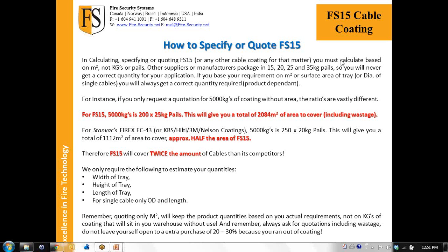But on top of that, one of the things is, as long as your machine is earthed, you're spraying live cable anyway. This is not a business interruption product. It can fix a business interruption as far as a fire in a substation after the fact, but spraying FS15 does not interrupt your business. You can do it live while that substation's running without issue. Wow.